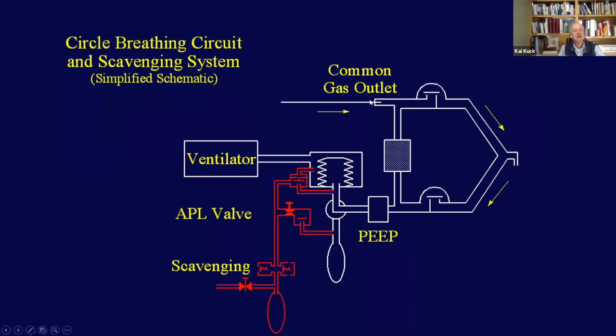When you do that, during inspiration fresh gas keeps going, and you actually end up filling the bellows larger with fresh gas. Most of the expired gas gets scavenged out. So on the next inspiration, most, if not all, of the gas that you're pushing out of the bellows is actually fresh gas. So that's basically one way of preventing this from being a circulatory system.